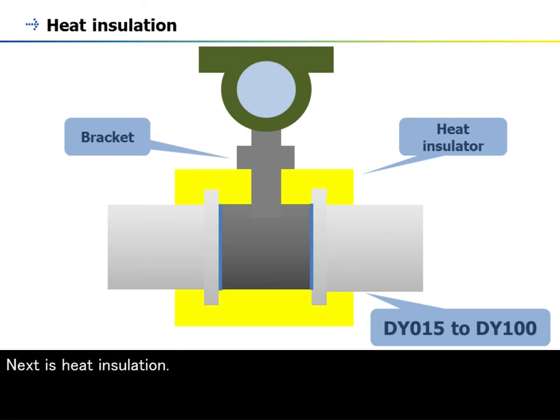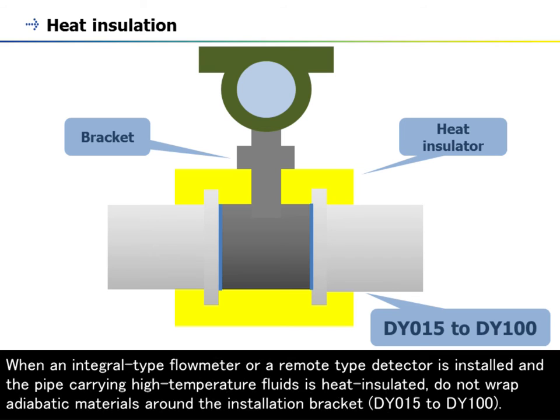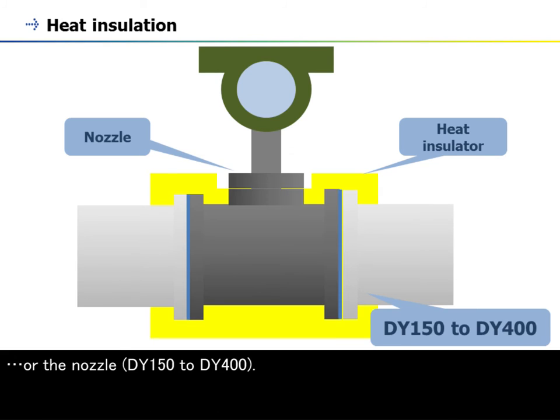Next is heat insulation. When an integral type flow meter or a remote type detector is installed and the pipe carrying high temperature fluids is heat insulated, do not wrap adiabatic materials around the installation bracket, DY-15 to DY-100, or the nozzle, DY-150 to DY-400.